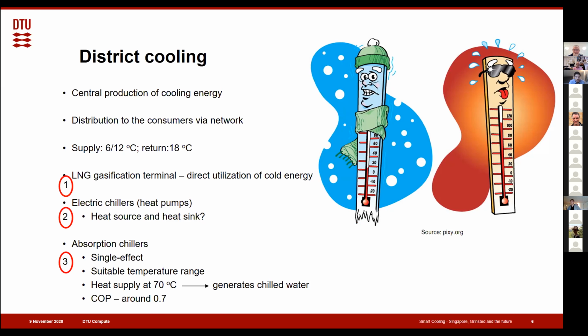If we do it as centrally distributed chilled water, which is more common approach in warm areas, we usually have a supply temperature of between 6 and 12 degrees and a return of around 18 degrees. So this is actually one very important distinction from a district heating system, that we have temperature difference of only around 12 degrees, which is much smaller than district heating grid, which has a temperature difference of 40 to 50 degrees. And the important consequence of this is that district cooling piping needs to be around 3 to 4 times larger diameter than district heating piping. And then we come to what could be actually sources of energy for this district cooling.